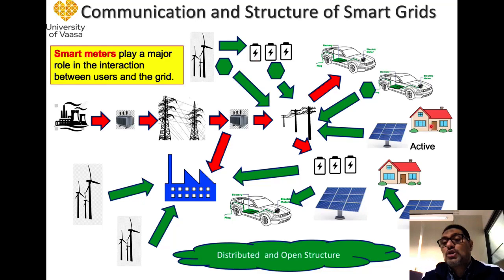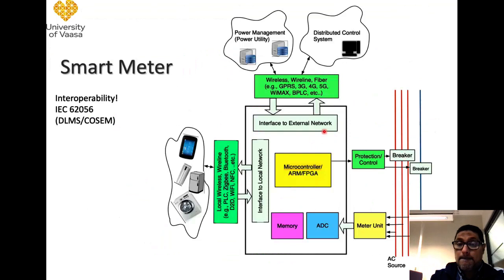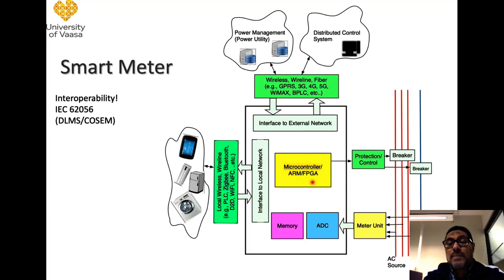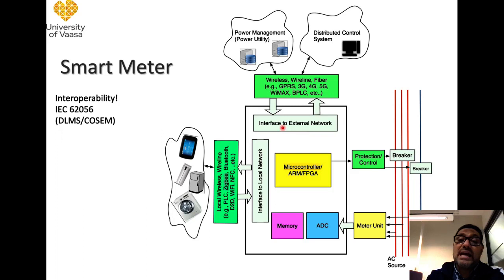Between customers, whether small or large, we always need to use a smart meter. This smart meter, or intelligent meter, is critically needed for the success of smart grid operation. At the heart of the smart meter, we have a microcontroller — which can be an ARM processor or FPGA — that controls the operation and runs the code containing all the intelligent functions of the smart meter. It is very important for the smart meter to be able to communicate with both the external and internal network.